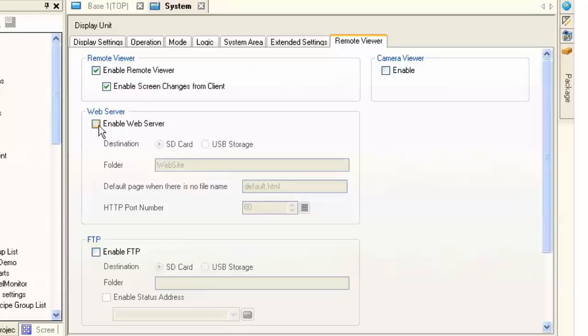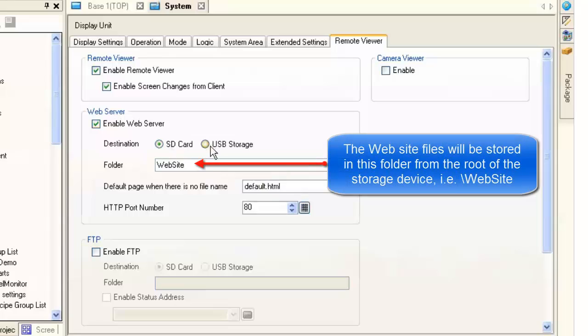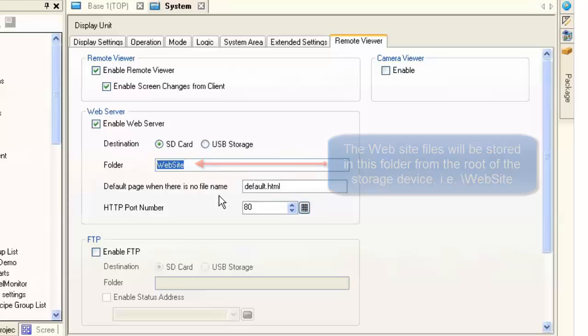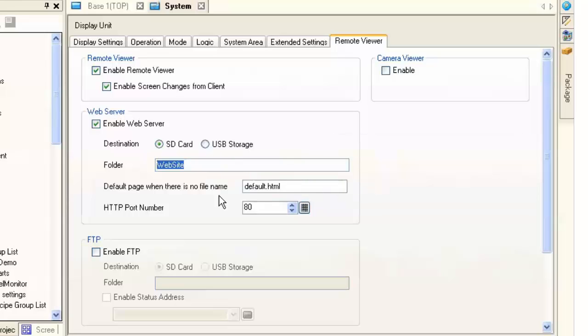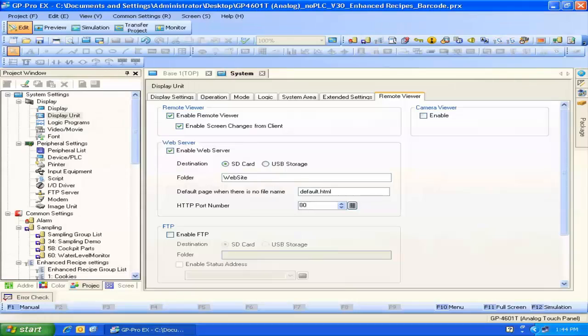All we have to do to enable the web server is check the box 'Enable Web Server.' In this particular case, using a GP4601, we have two choices: an SD card or a USB storage device. We're going to use an SD card today. All the rest of the options here can be left as defaults. The 'Website' folder is where it stores data in the root folder on the SD card. That's all we need to configure the web server.